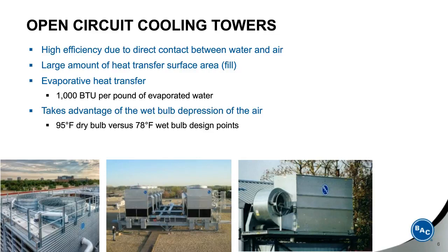And that's the last point, where the cooling tower takes advantage of what is called the wet bulb depression of the air. In Baltimore, on a 95-degree day, you can have a 78-degree wet bulb. Thus, you can cool the water down below the dry bulb of the air and get very efficient temperatures back to your cooling load.